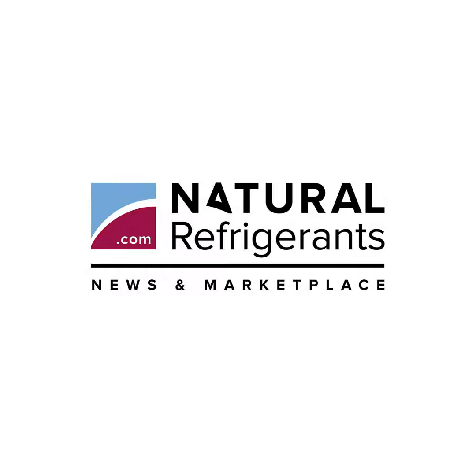As a natural refrigerant, water has many advantages. It has a high heat of vaporization, 2,260 joules per gram, is non-toxic, non-flammable, and not an asphyxiant, and it presents no safety or environmental issues, 0 GWP and ozone depletion potential, and no PFAS. Furthermore, O'Connor emphasized, it is fully retrofittable to existing installations without changing the piping to the evaporators. In addition, as a closed-loop system, it does not waste water.